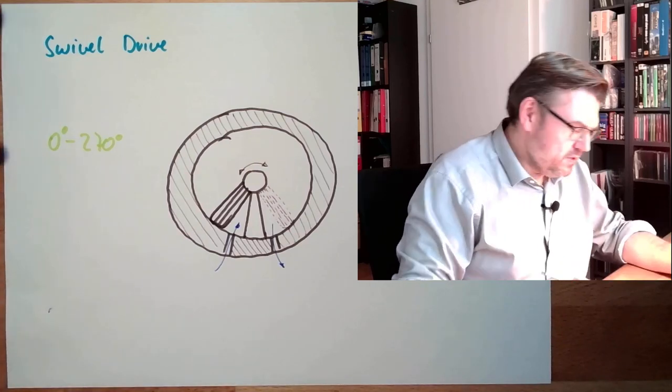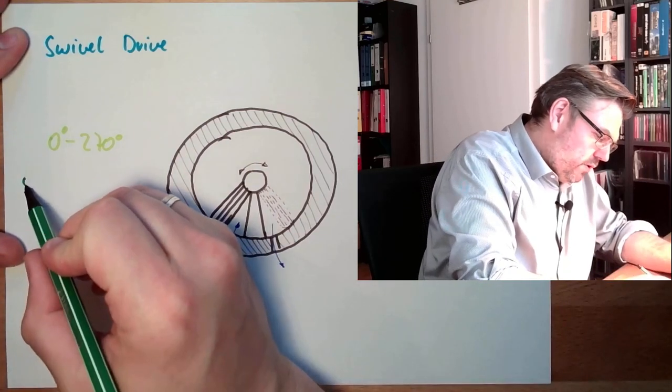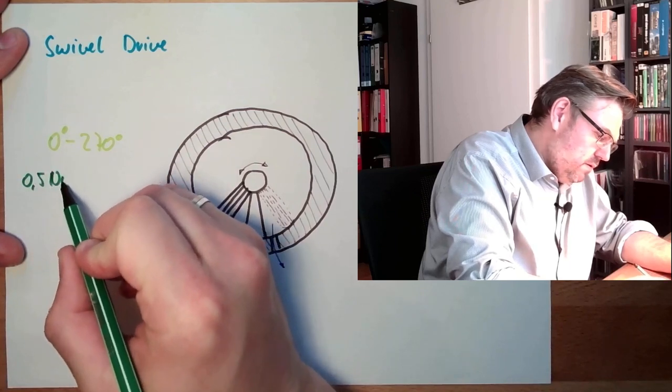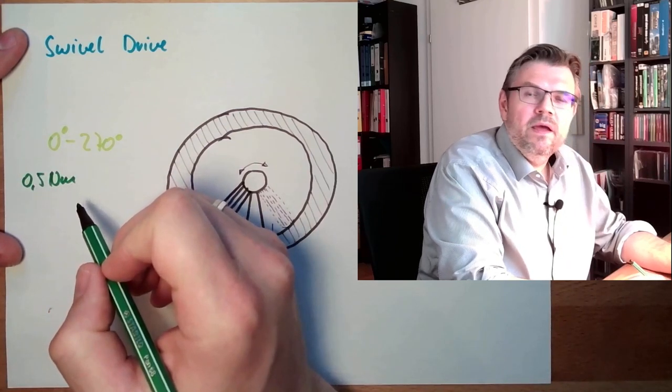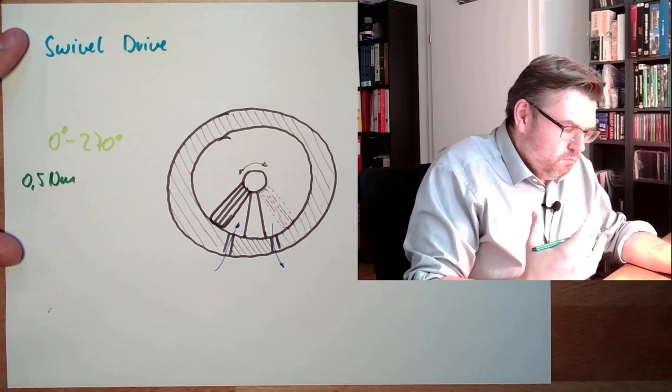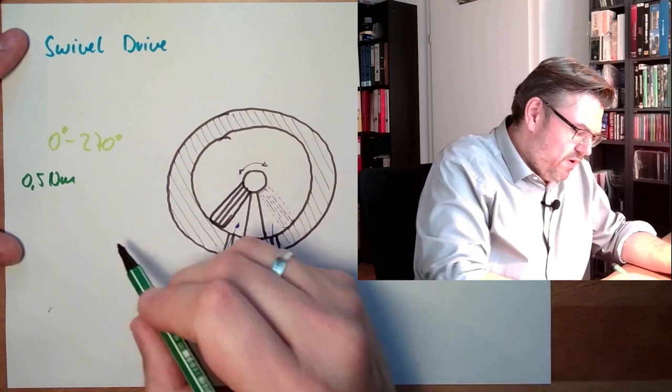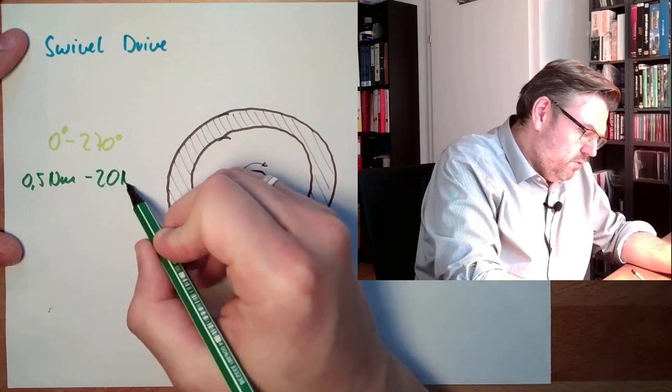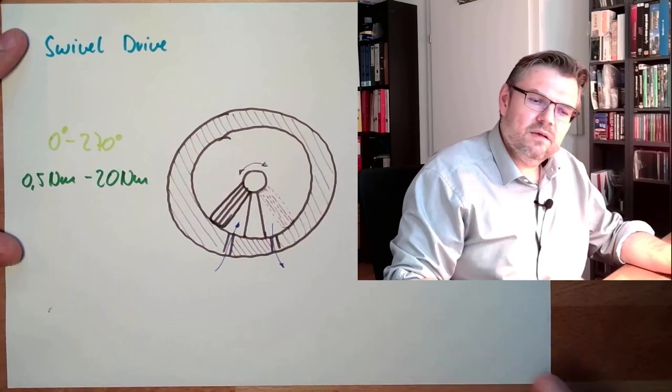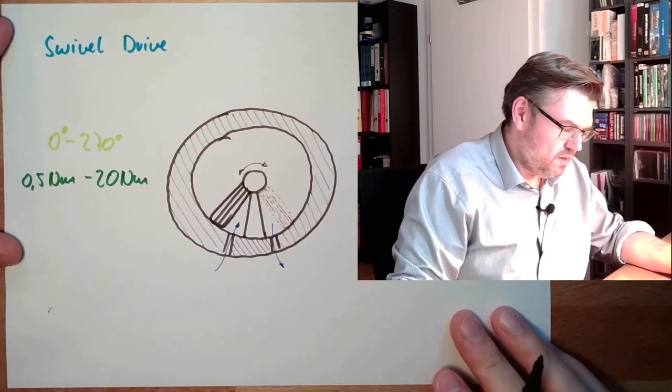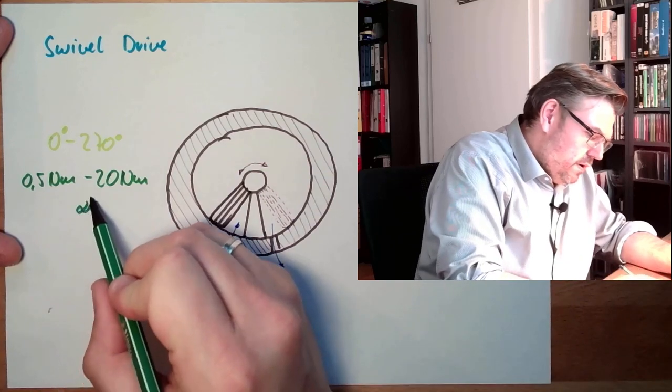And of course, there is also the torque. The torque can be 0.5 Nm, so small. And the maximum torque - it depends a little bit on the size of the flap, of course - but it would be 20 Nm. So a little bit less than the rotary cylinder, also at 6 bars.